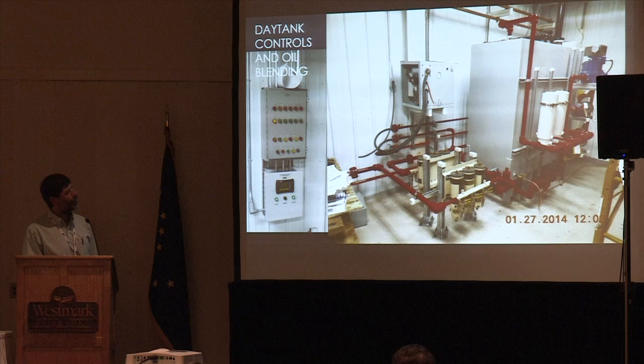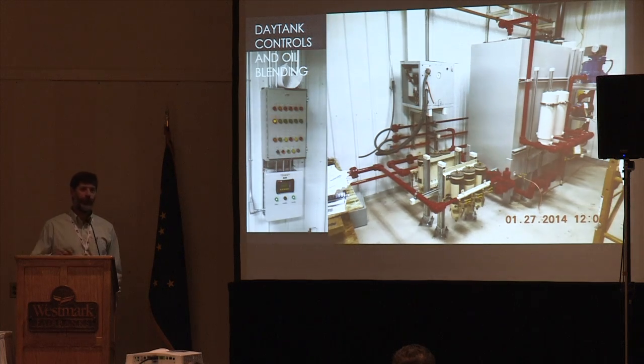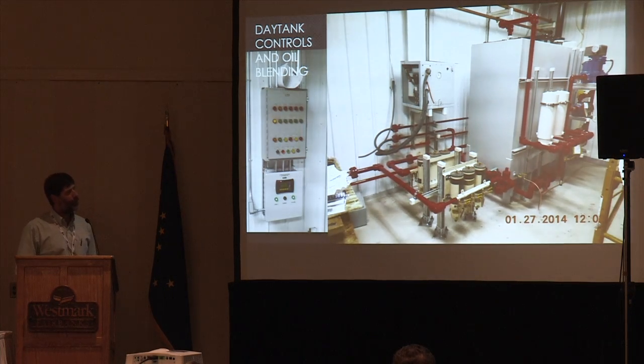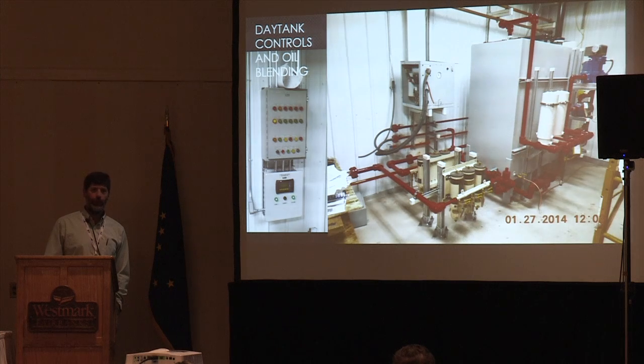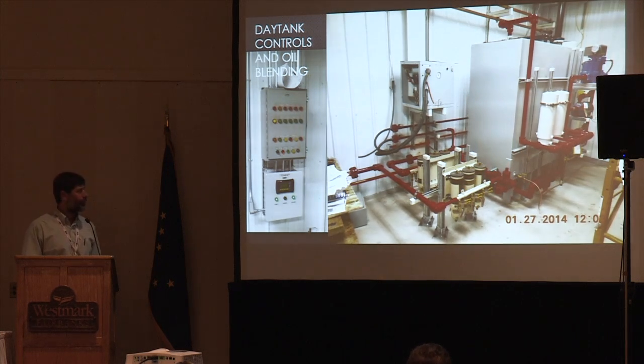This has got an oil blender on it, so as you're pumping fuel into the day tank, it'll recirculate and pull oil out of a hopper. Whenever they change oil, they can put it in the hopper, and it'll blend that oil back into the fuel so you can burn it, rather than bringing it outside to burn in a smart ash burner or trying to ship it off site.